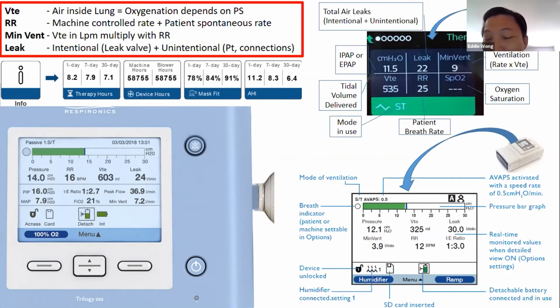But let's say 4 is normal for you. You can set 3 as your low minute ventilation alarm. If anything goes below 3, the machine will alarm and inform you that a low minute ventilation is achieved on the patient. Then you need to take some action on your patient. What action do you need to take? Minute ventilation is related to rate and tidal volume, right? So first thing, you look at your rate. Has the rate dropped below what was prescribed by the doctor?